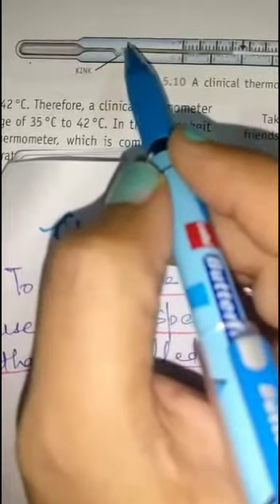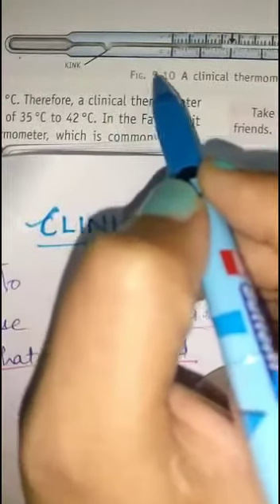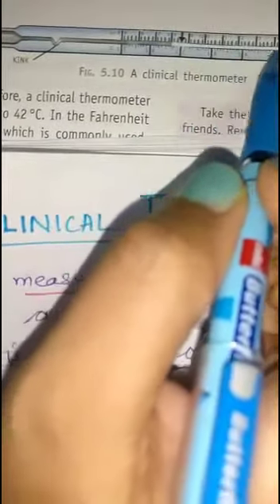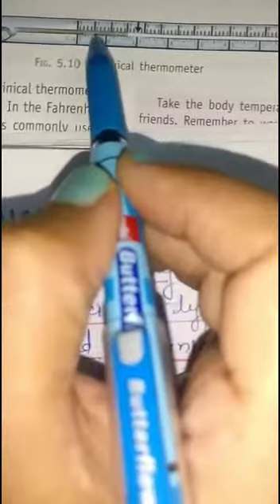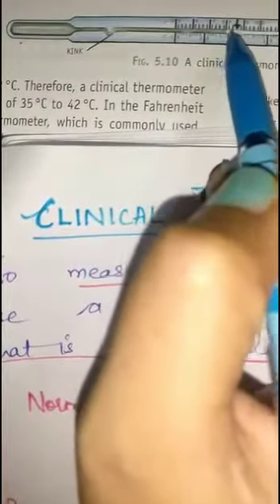In the clinical thermometer, there is a kink in the stem just above the bulb. When the thermometer is taken out of the mouth, the liquid in the bulb contracts and the mercury column breaks at the kink. Therefore, the level of mercury in the stem remains the same, so the reading does not change even after removing the thermometer from the mouth, giving an accurate reading.